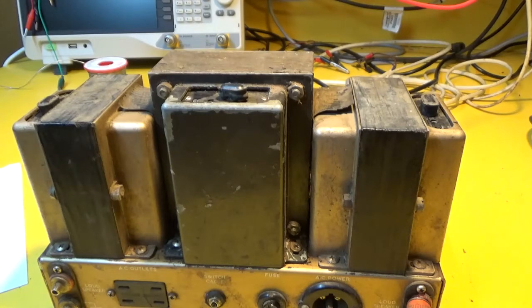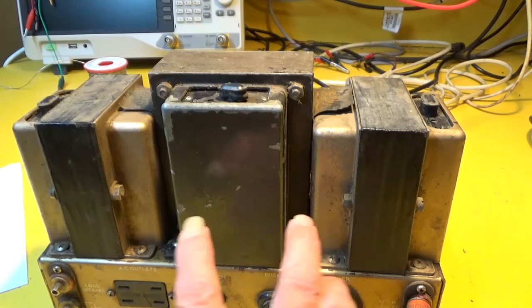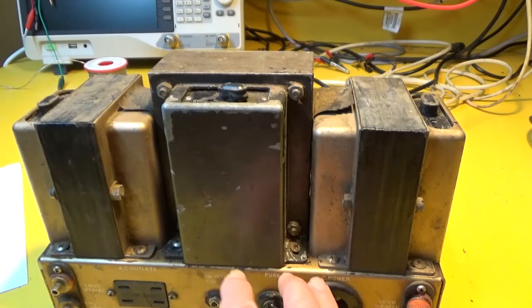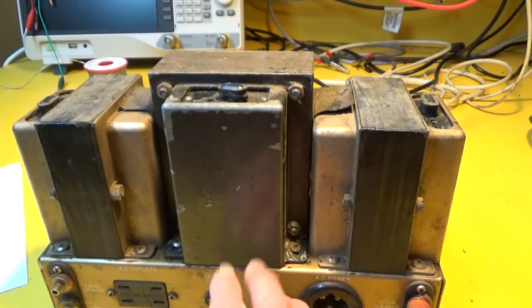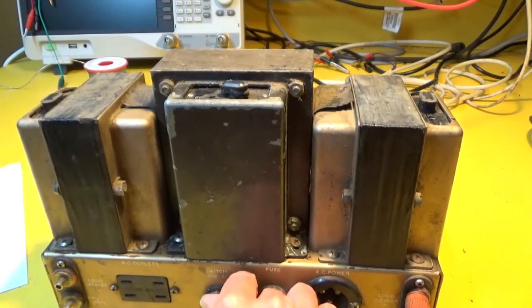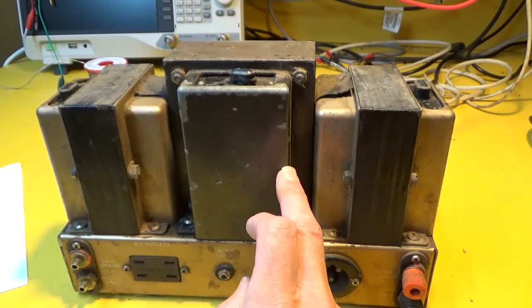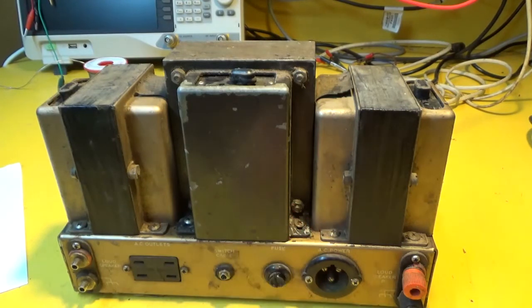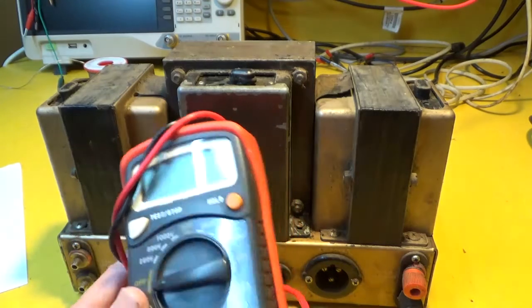But I thought, I'll stick some voltage on it, a low voltage, onto the primary and see what I get out of the secondary before I stick full mains on it. But before I did any of that, I thought I'd put it back in the chassis and wire it all up again, and test the insulation resistance between the chassis, in other words earth, and the primary using my insulation tester, which is what electricians use for house wiring testing.